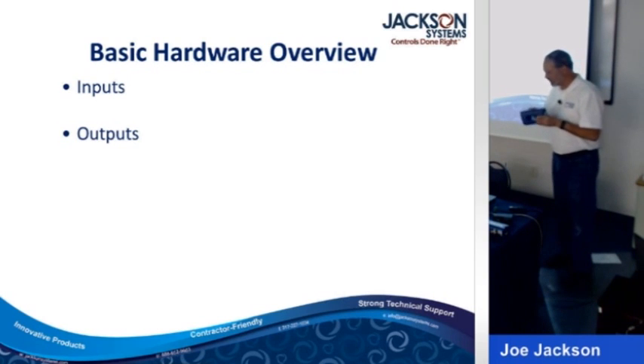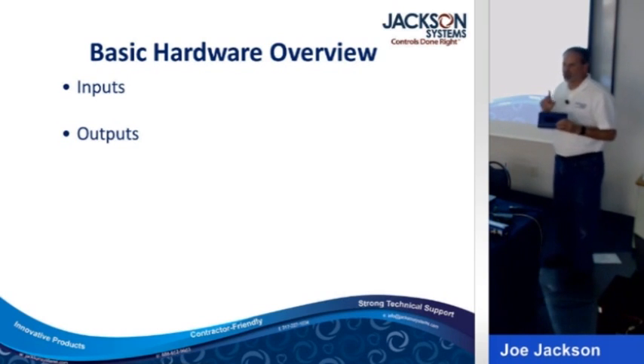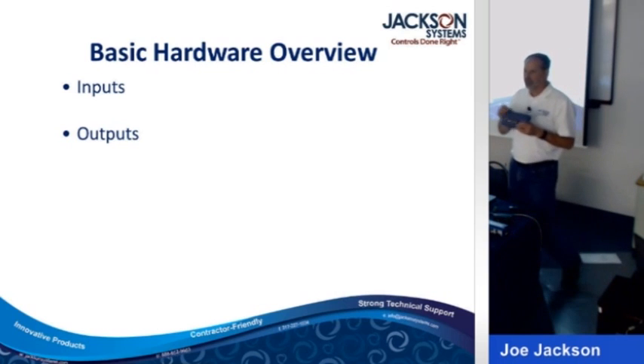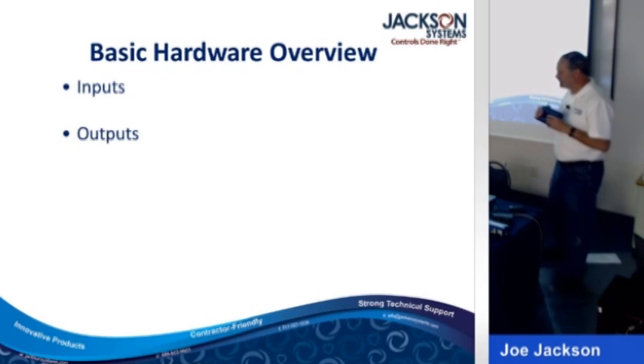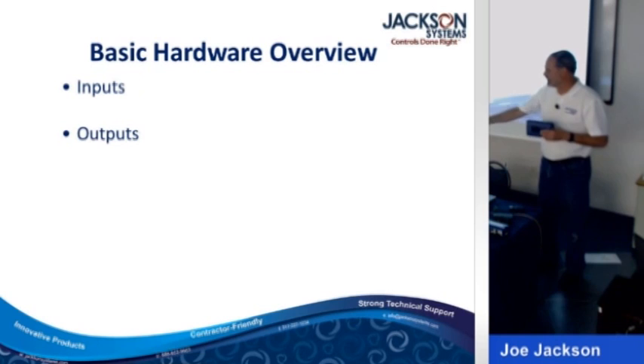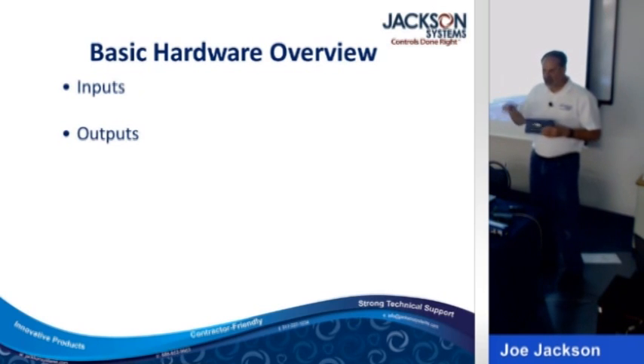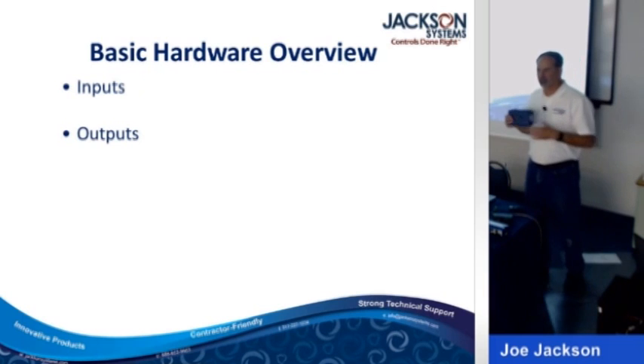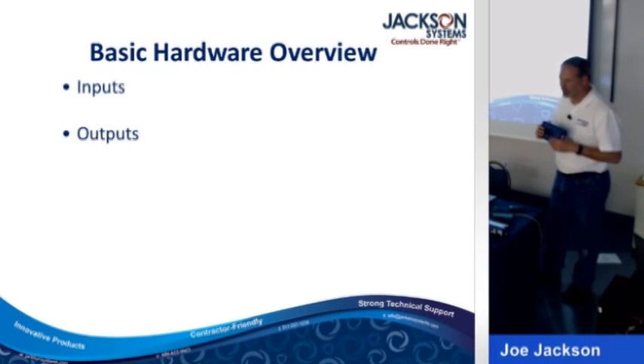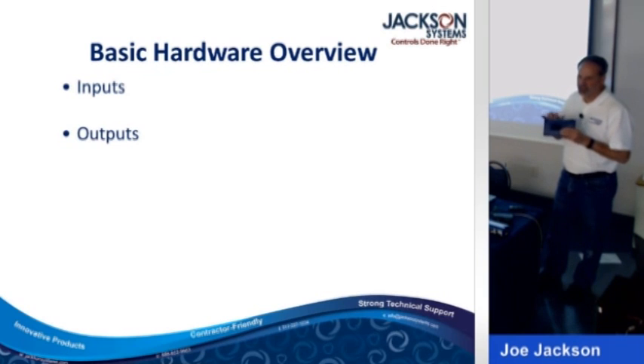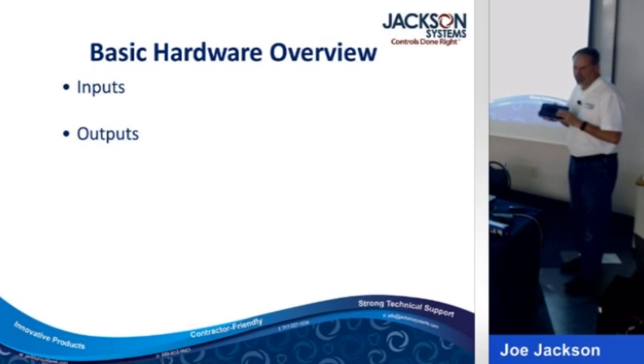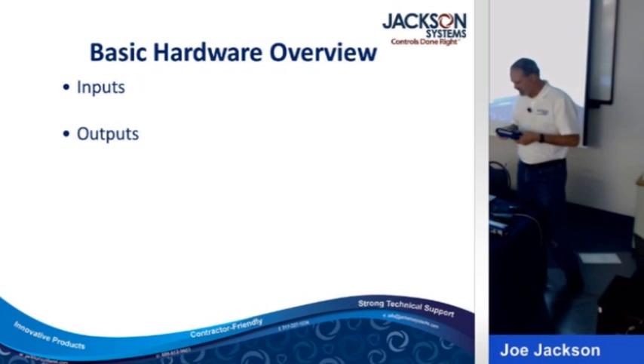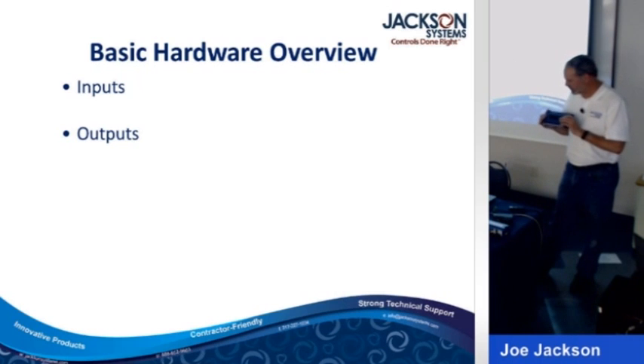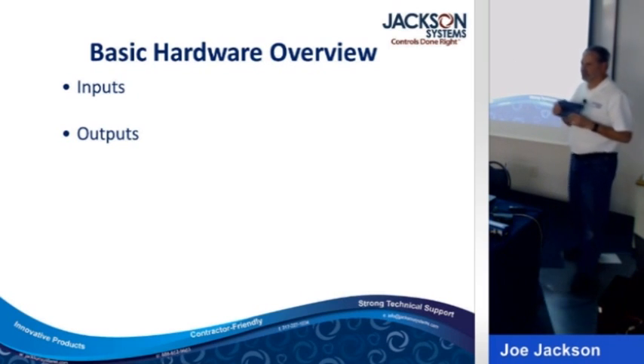And I don't know if anybody cares, but the way it really works is this little controller puts out 5 volts DC. If you tell it it's a digital, it's just looking for that 5 volts to come back on the other wire. If it comes back on the other wire, it knows the contact's closed. If you tell it it's a thermistor, it puts the 5 volts out through the thermistor, and by how much of that voltage comes back, it can calculate what the resistance is, and therefore it can calculate what the temperature is. So this guy just puts out 5 volts DC. There's nothing spooky about it. If you had any questions about whether the input was still good, you could actually stick a DC voltmeter on there to see if the 5 volts is there. That would give you an indication whether it was a problem or not. Does that answer that one?